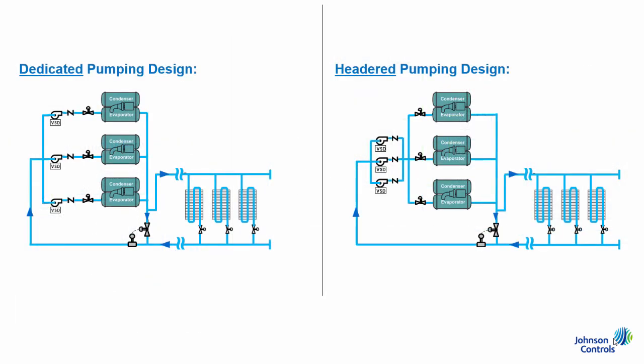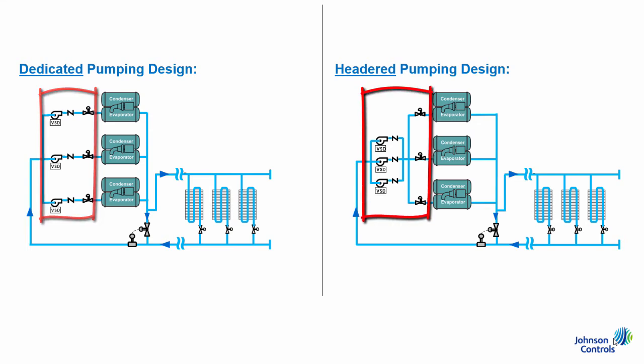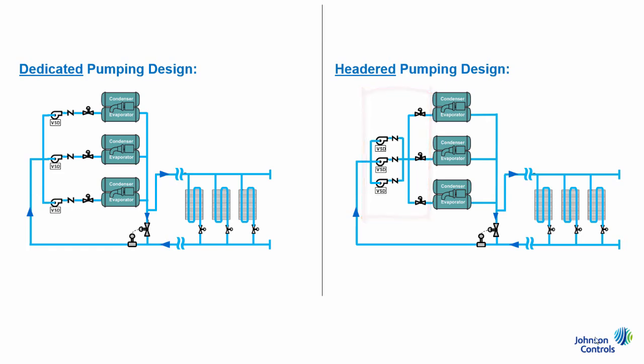One additional item to note regarding pumps is that VPF pumps can be arranged in a chiller-dedicated design, meaning they directly support each individual chiller, or in a header design, which is much more common. The headered approach allows all pumps to contribute to the system flow, independent of the number of chillers. This is typically preferred by the consulting engineering community, as it allows for improved system energy optimization opportunities. For example, when the system is operating at part load, a control strategy could be implemented to optimally balance the load across several pumps to help maximize system efficiency. This is a more difficult task with a dedicated pumping arrangement.